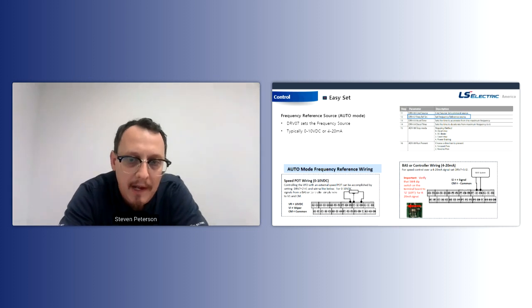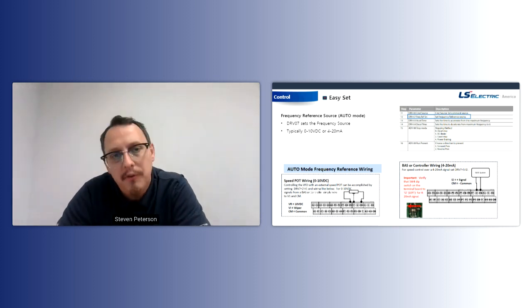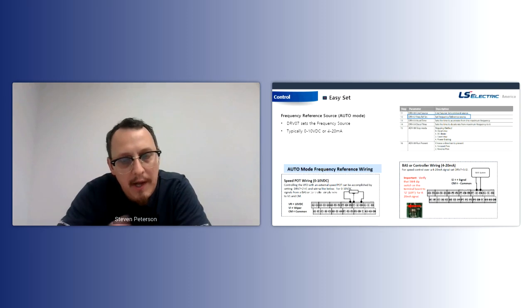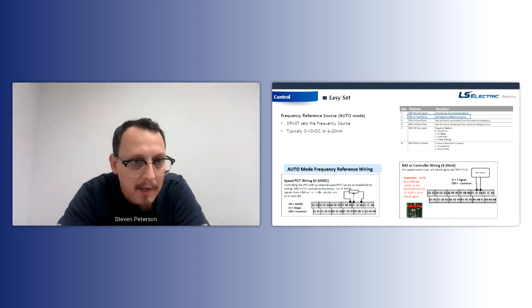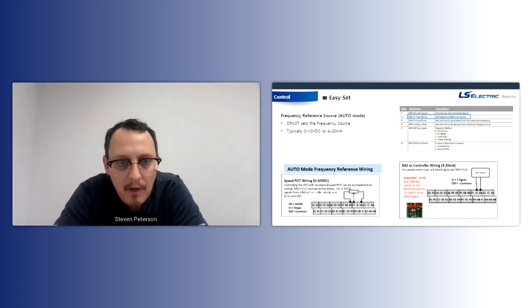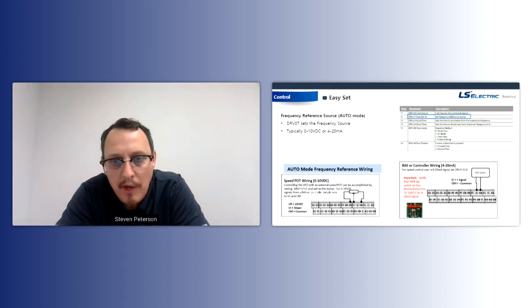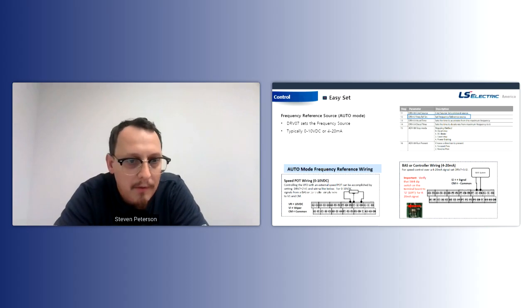And to follow on that, you always need two things to start the drive. You need a run signal, and then the second thing you need is a speed command. So your speed command is what we call our frequency reference source. It's the next parameter down, DRV7. Most of the time, guys are running either a 0 to 10 input or a 4 to 20 milliamp input. Okay, so here's some pictures on the bottom that kind of show you some basic wiring diagrams.